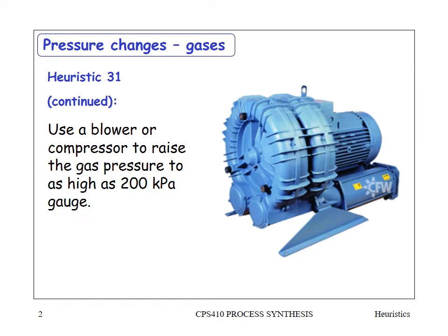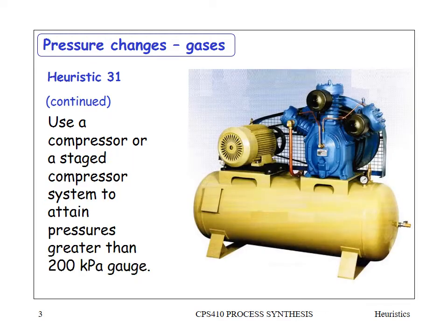Continuing with heuristic 31: use a blower or a compressor to raise the gas pressure to as high as 200 kPa gauge. Between 10 and 200 kPa gauge, one application would be to drive a fluidized bed where you need to blow gas right through a bed of sand, requiring more pressure than the mere 10 kPa. What's shown is a side-port blower — this is what we use in the pilot bay in Engineering 2 to drive the dual fluidized bed pyrolysis apparatus, including a two-stage side-port blower.